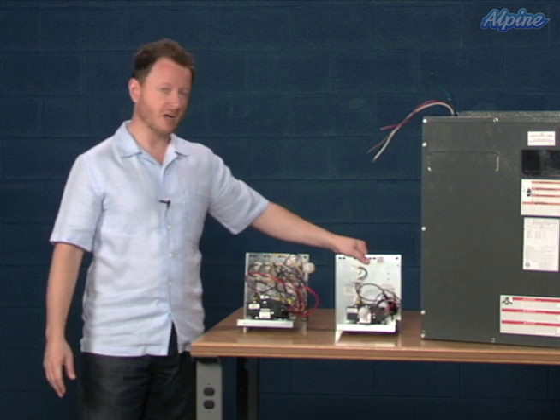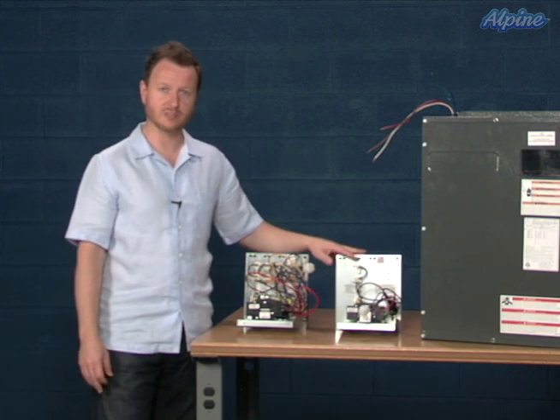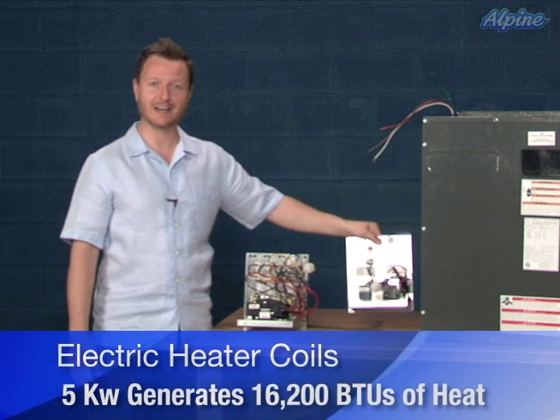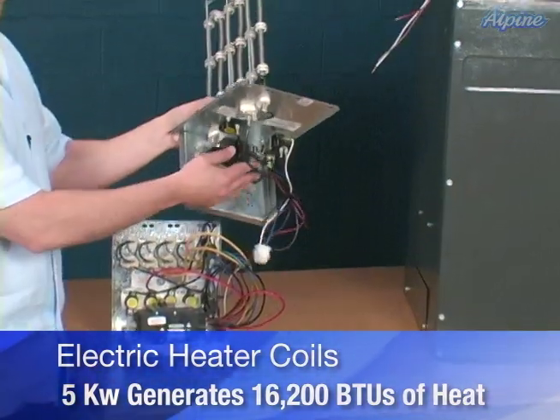Now, electric heater coils come in several different capacities. The larger the capacity, the more heat it provides. On the low end of the spectrum, we have here a 5 kilowatt heater coil and this puts out about 16,000 BTUs of heat and it operates on a single 30 amp electrical circuit.